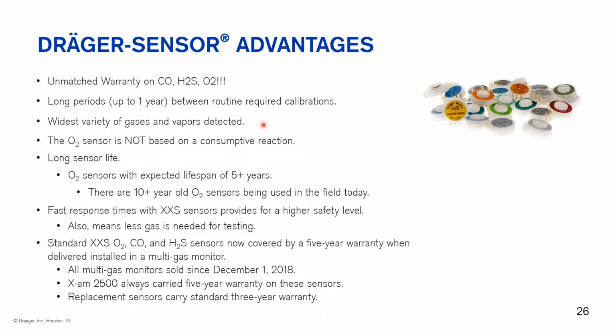So, just summarizing things here: the warranty on CO, H2S, and O2 sensors is the longest in the industry, with long times between required calibrations and a very wide variety of gases and vapors detected. Our O2 sensor is not a consumptive-based reaction, so we're going to get extremely long lives on our O2 sensors. We do actually have units in the field with 10-plus-year-old O2 sensors that are still working almost like brand new. Again, the fast response times give us that higher safety level I talked about, and also translate to less gas needed when you're doing the function tests and calibrations.